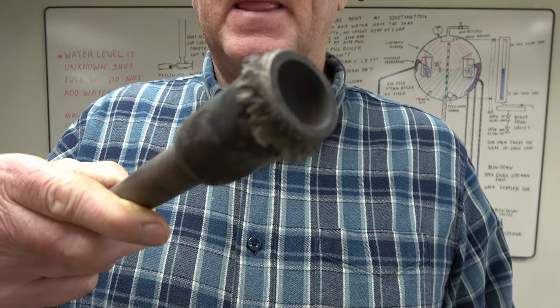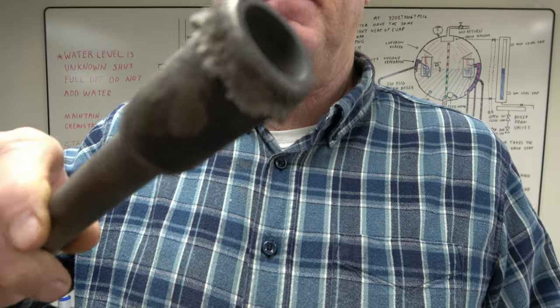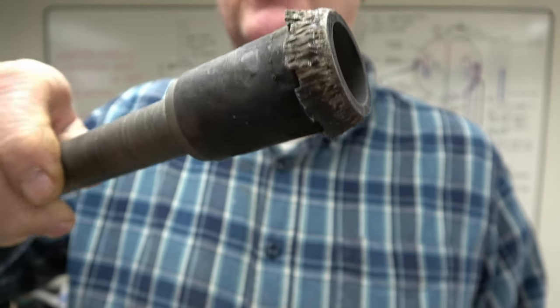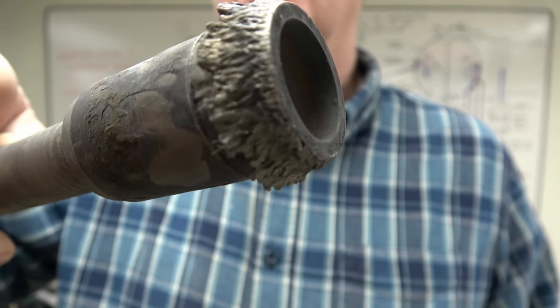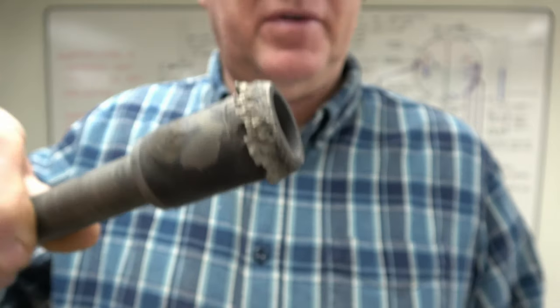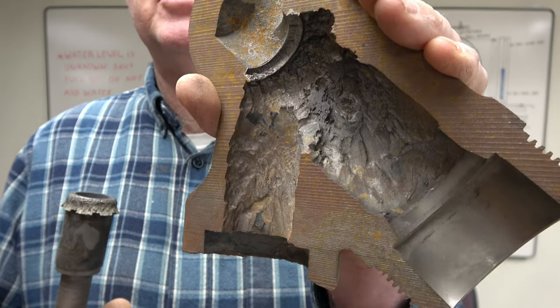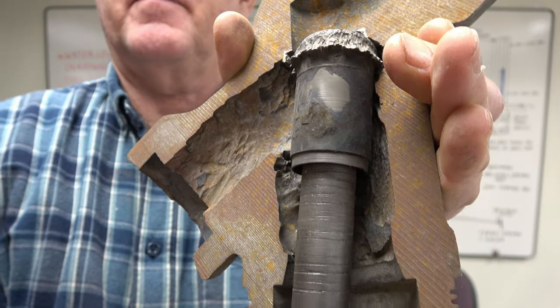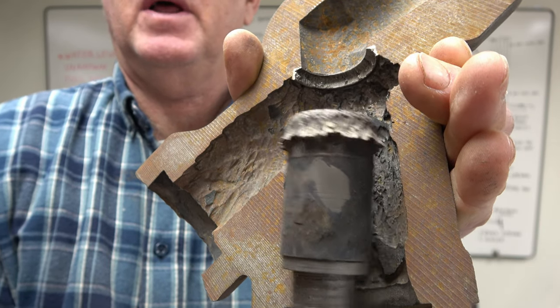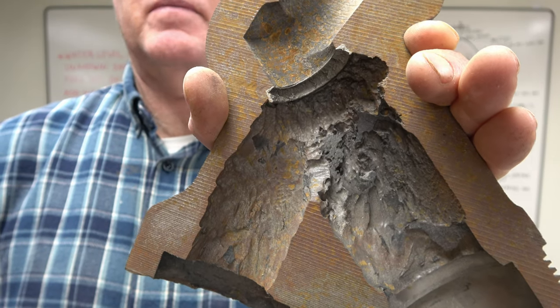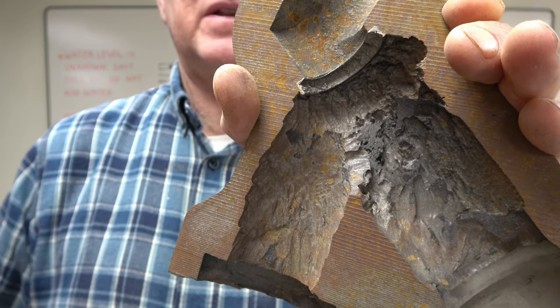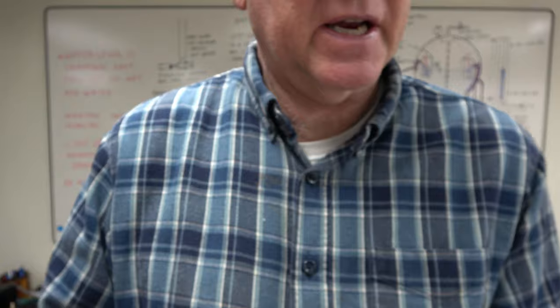Okay we got some samples here of valve damage. This is part of a stellite seat valve. As you can see it's been pretty well destroyed. They have a steam water cut. It's amazing it has this much energy to do this. There's nothing left of the sealing surface on this valve. Here's the body. As you can see it's substantial damage cut through the stellite seat. This valve sat in here like this. As you open it it pulled down. Anyhow it's pretty well destroyed this valve. That's why once these valves start leaking through they get cut. That's the end of the valve. When you start a plant up it's a good idea to take a heat gun out just to make sure valves aren't leaking. Sometimes you can tighten them down a little bit more and prevent this kind of damage. That's why you use one valve for sealing and one valve is used for throttling the flows.